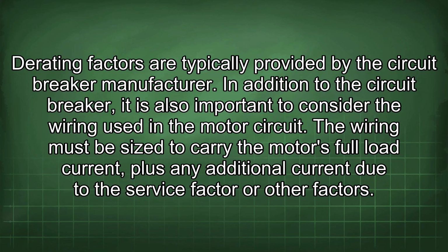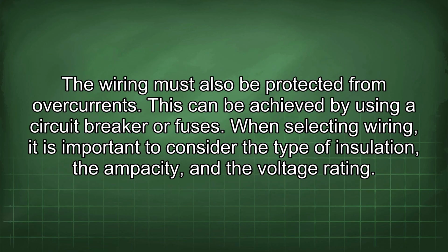In addition to the circuit breaker, it is also important to consider the wiring used in the motor circuit. The wiring must be sized to carry the motor's full load current, plus any additional current due to the service factor or other factors. The wiring must also be protected from overcurrents. This can be achieved by using a circuit breaker or fuses.